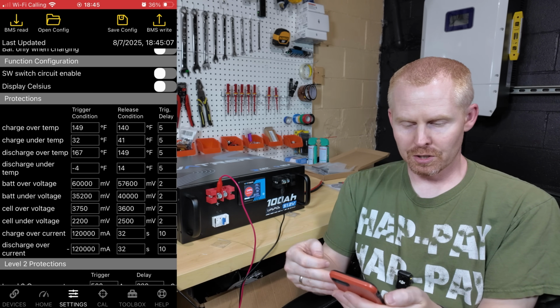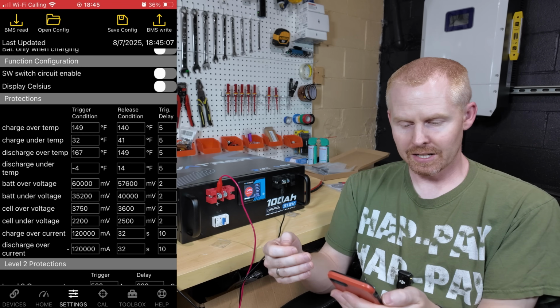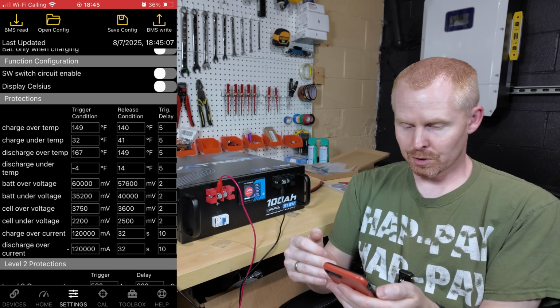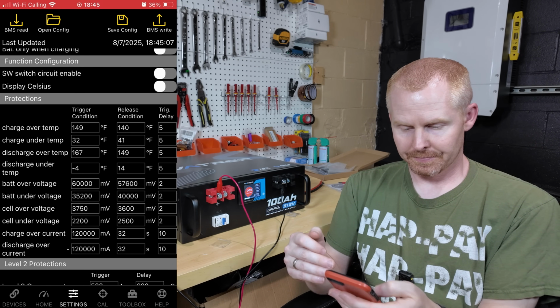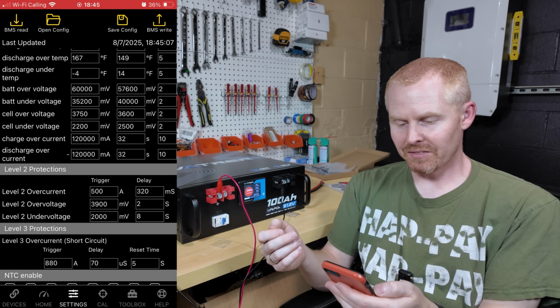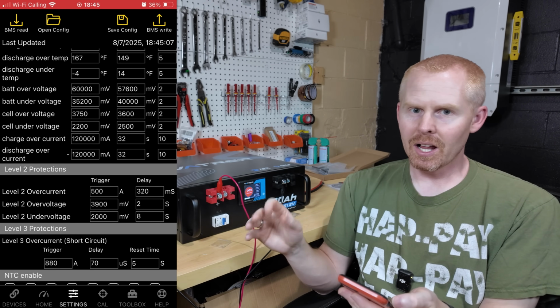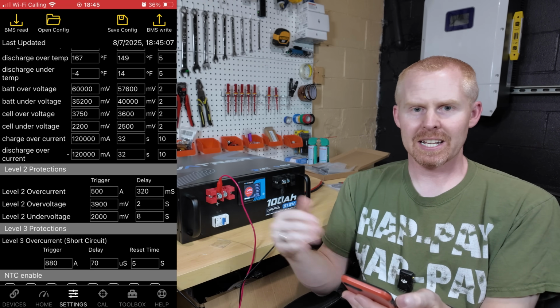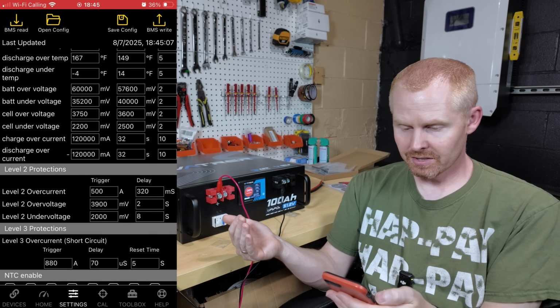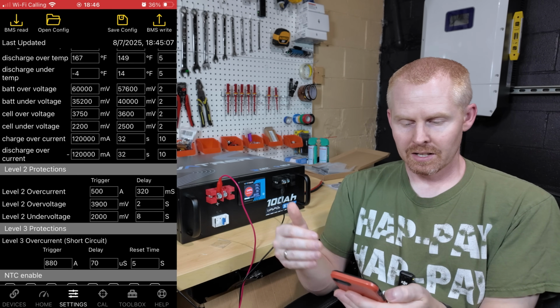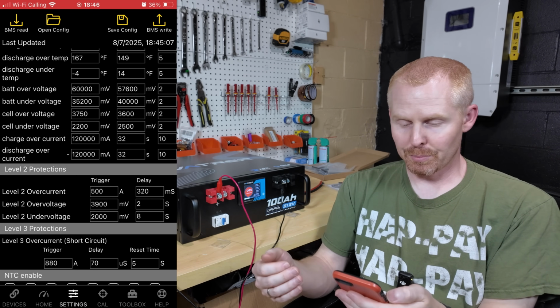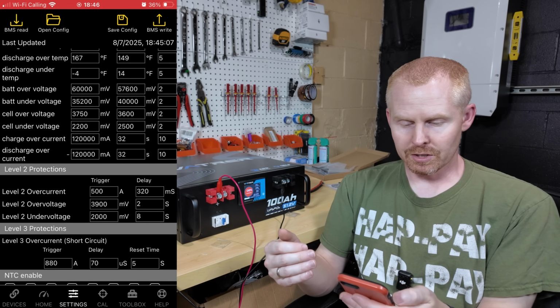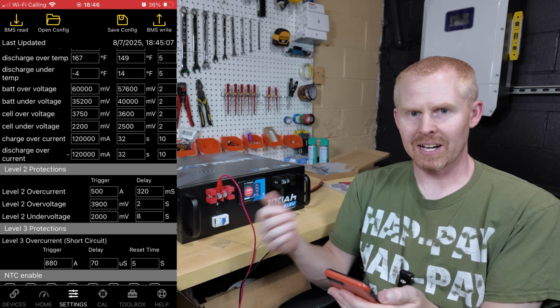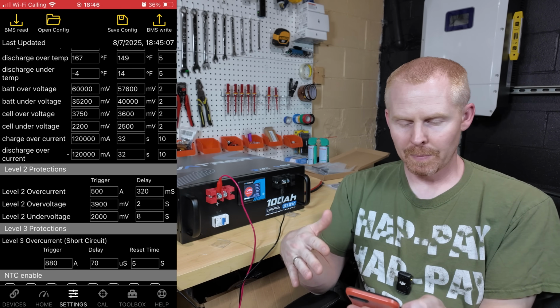Our charge over-temperature protection is 149 degrees, charge under-temperature is 32 degrees. Cell over voltage is 3.75, a little high for my taste, I like to see it right at 3.65 volts. They have it at 3.75 and releasing at 3.6. Cell under voltage is 2.2 and releases at 2.5, which again is a little low.